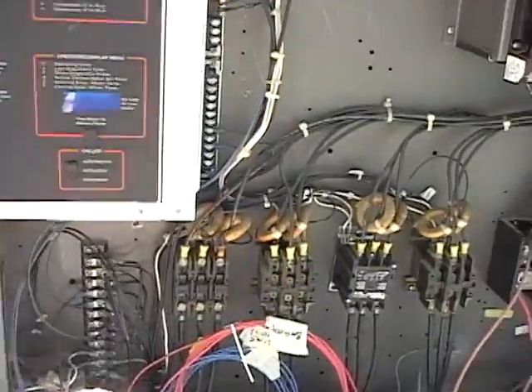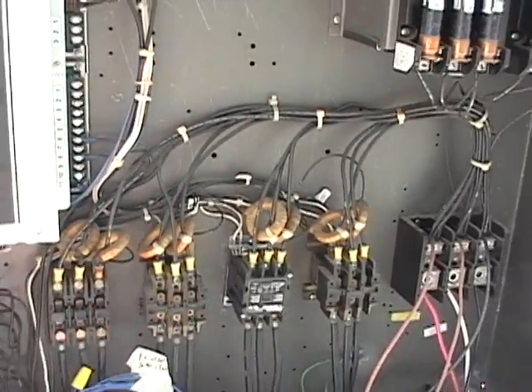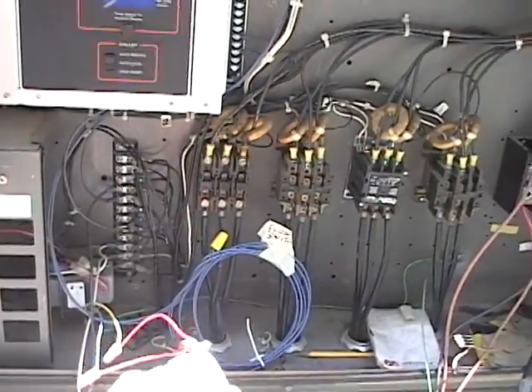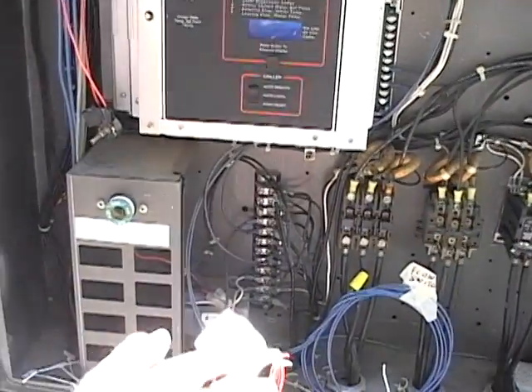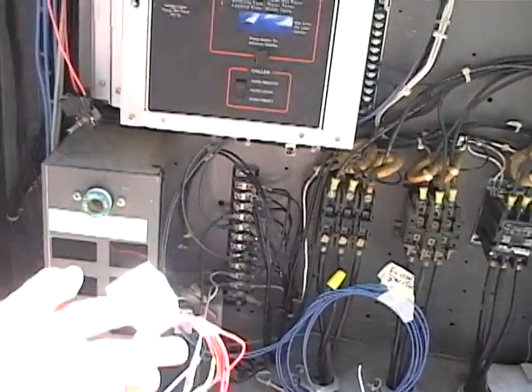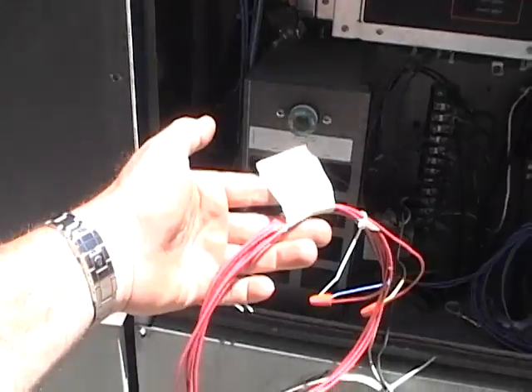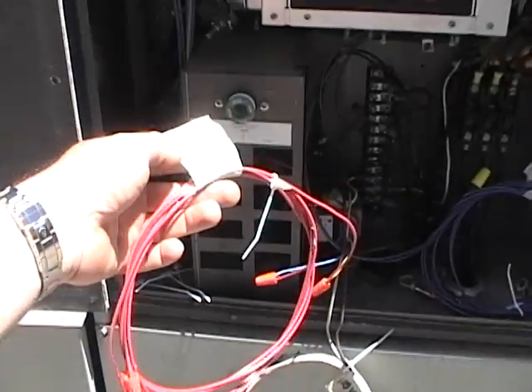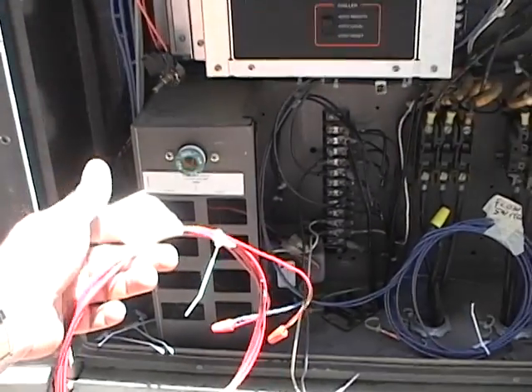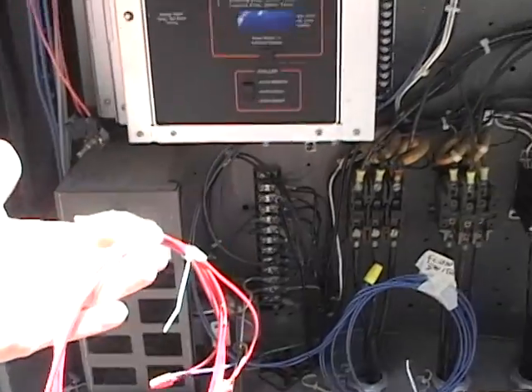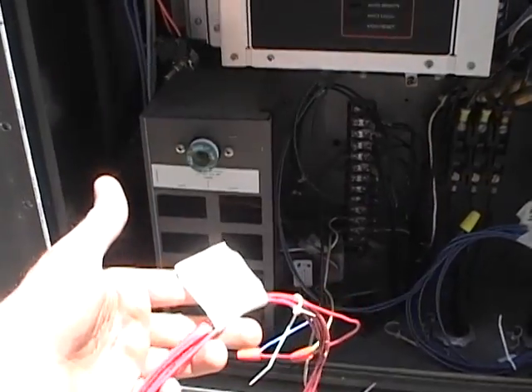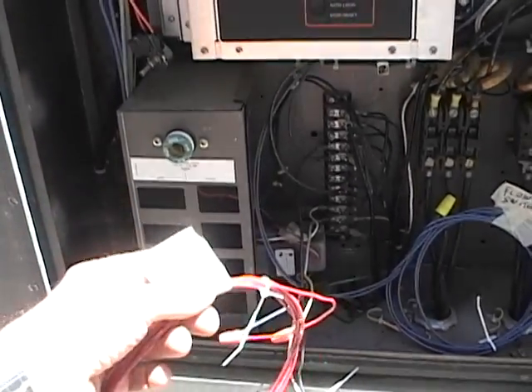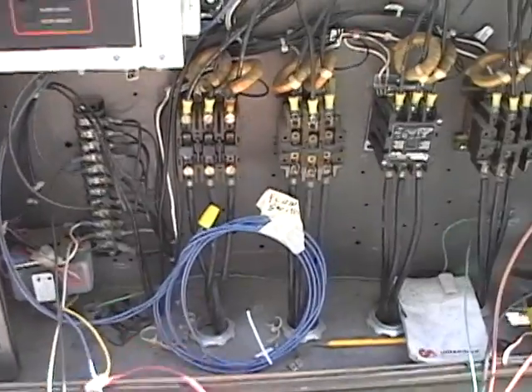They had this unit running an air handler in a building as well as a process for a factory making plastic profile. So there's one right over here. There's a low voltage set of wires which I've marked building. These right here could be put to an air handler if you want. If not, you can use 100% of your capacity for whatever else, you know, for your process water.